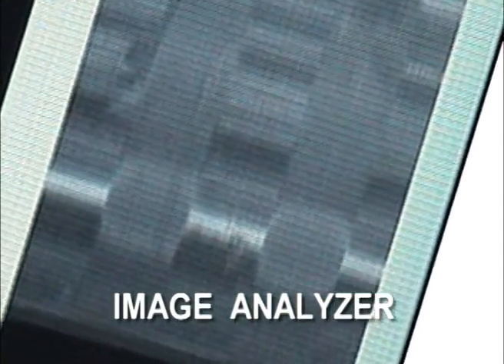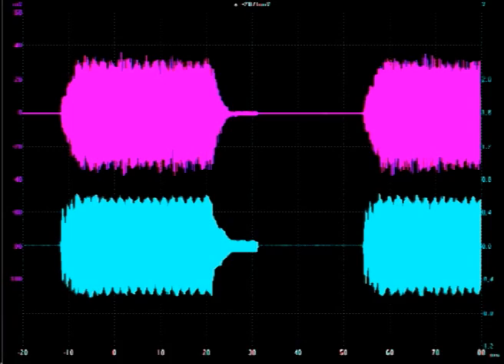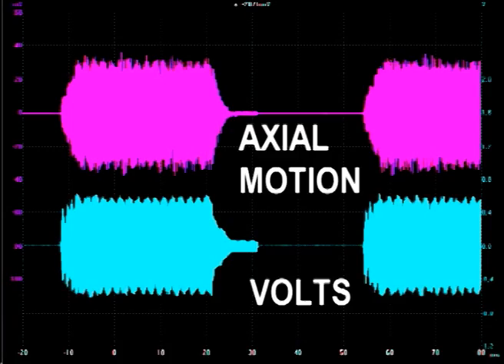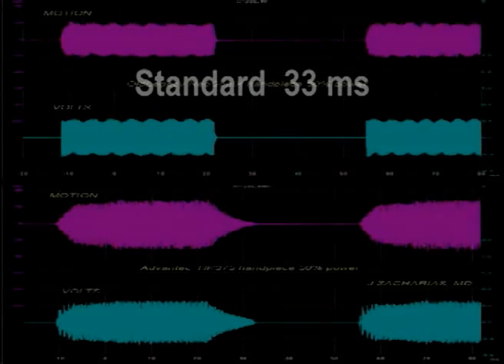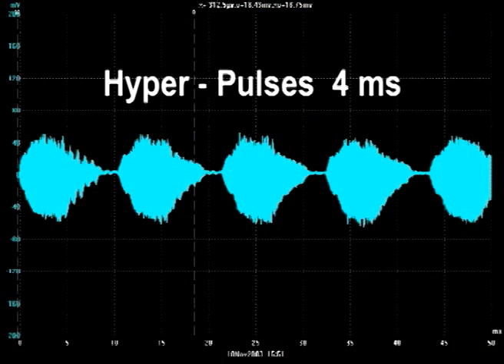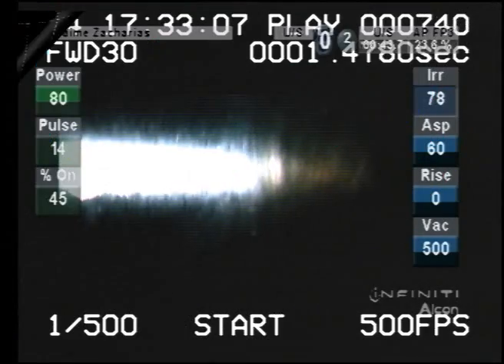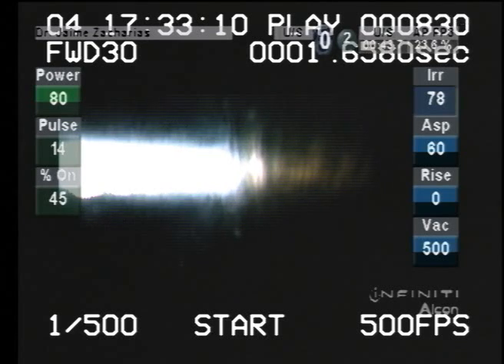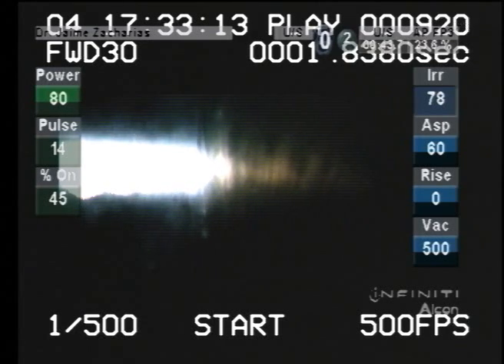Using our image analysis software, and with greater detail using a proprietary optical interference method, we have determined the anatomy of a standard ultrasonic pulse and of hyperpulses, an important step to understand tip-tissue dynamics.